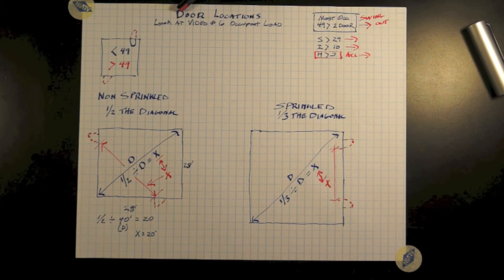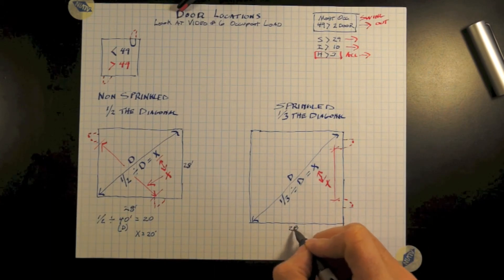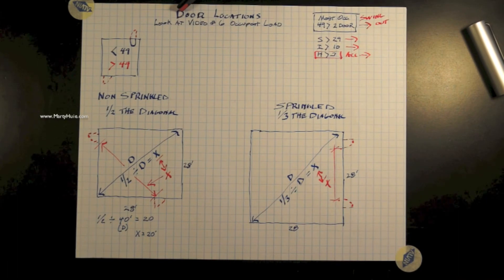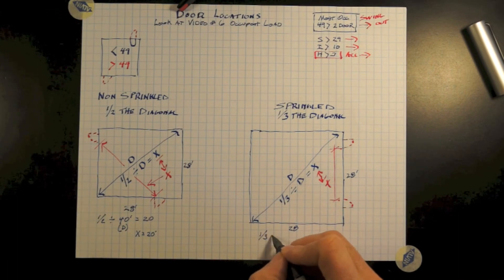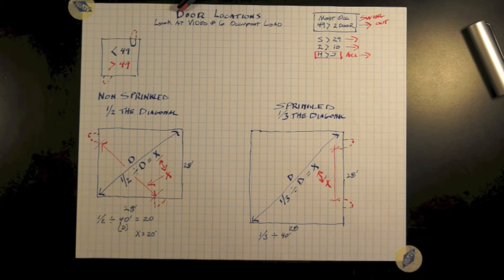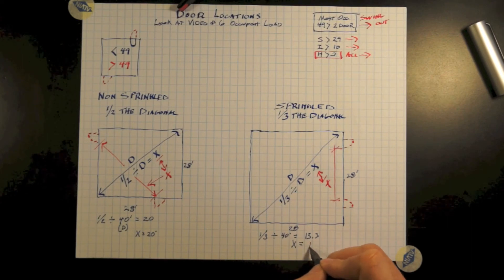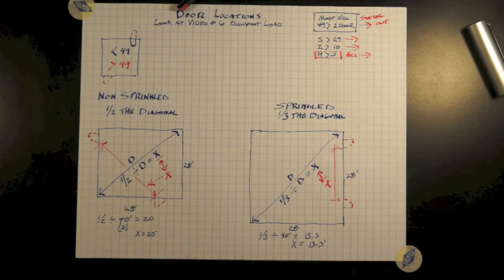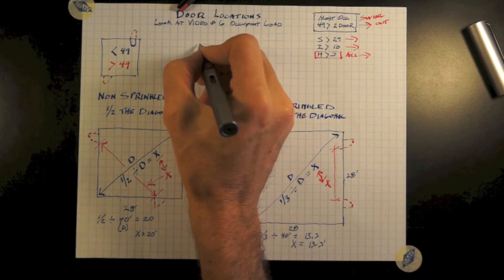On sprinkled buildings, let's take the same dimensions, 28 by 28, our diagonal distance is 40. So 40 feet divided by three equals 13.3 feet. So therefore, our doors cannot be closer together than 13.3 feet.